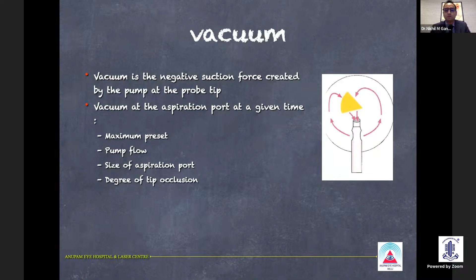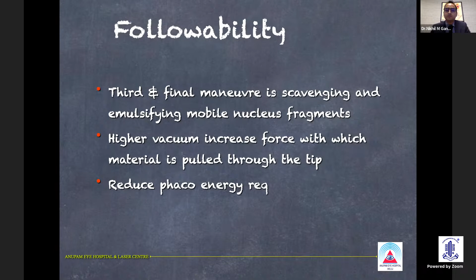Coming to the vacuum part, which is the negative suction force created by the pump at the probe tip. And followability is the third and final maneuvering in scavenging and emulsifying the mobile nucleus fragments. Higher the vacuum, the greater the force with which the material is pulled through the tip, which reduces the energy that is really required. And then coming to the rise time, the time taken by the system to reach the maximum vacuum setting once occlusion takes place. So in peristaltic machines, there is slow rise time and good safety margin, and the rise time can be decreased by increasing the flow rate. Whereas in the Venturi system, there is rapid rise time due to high flow rate.